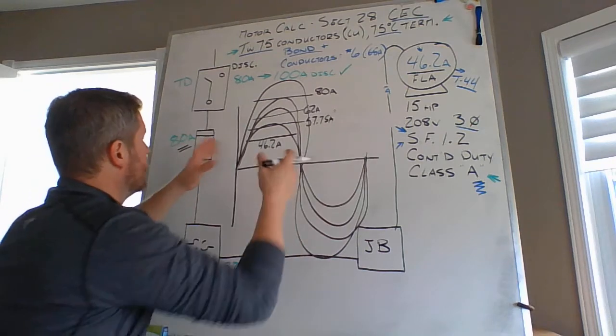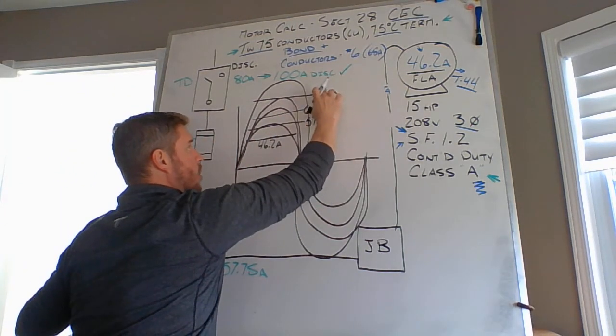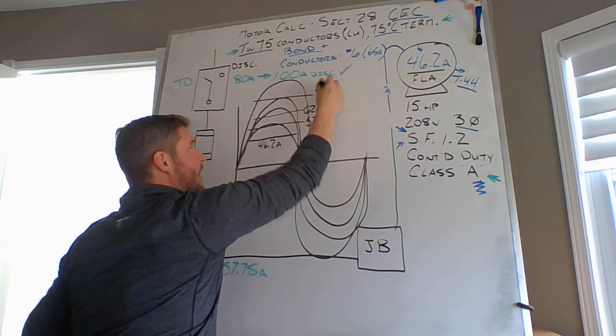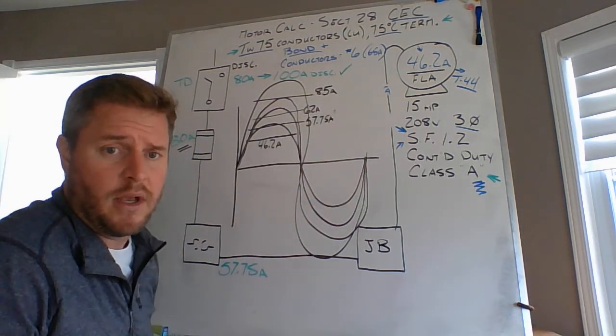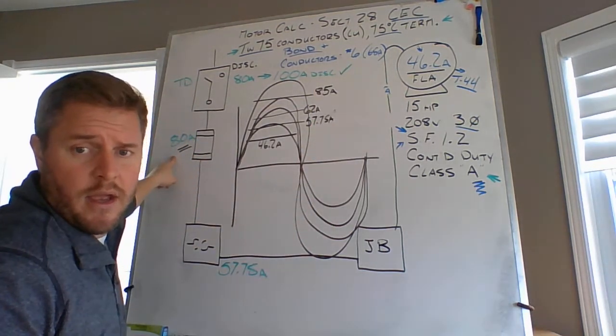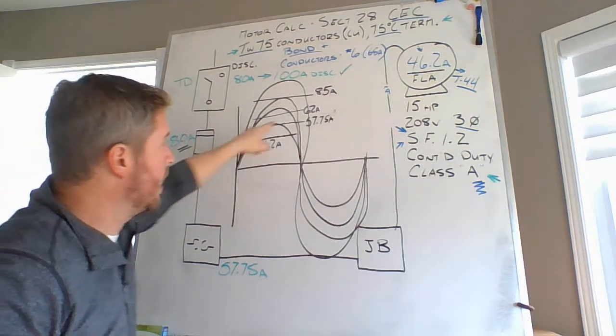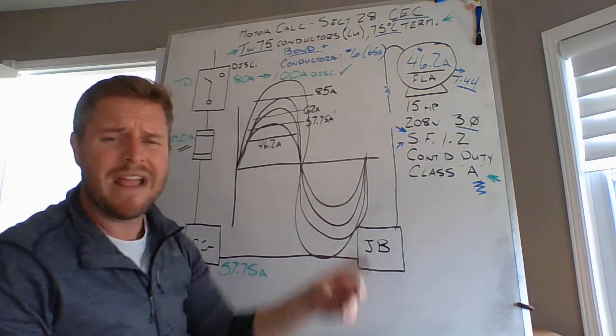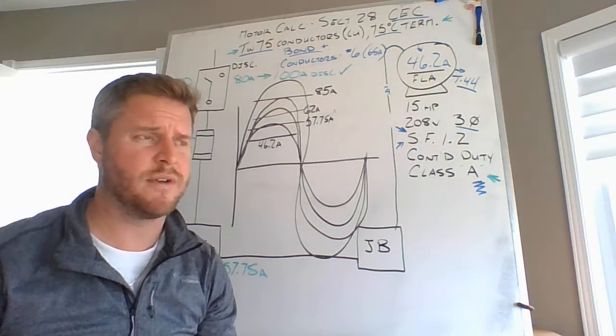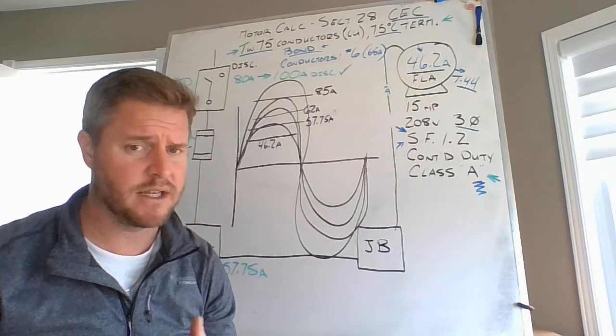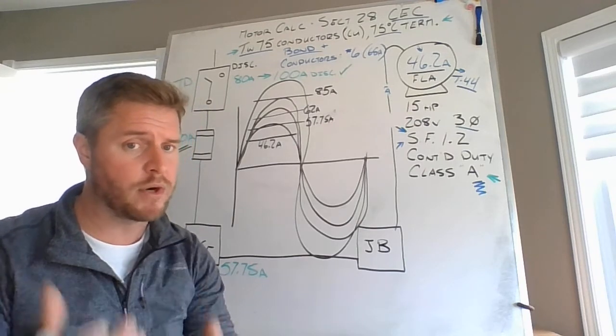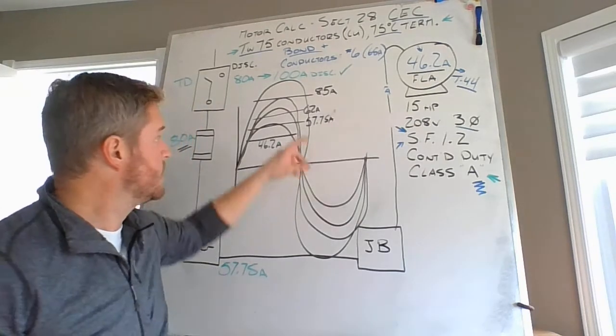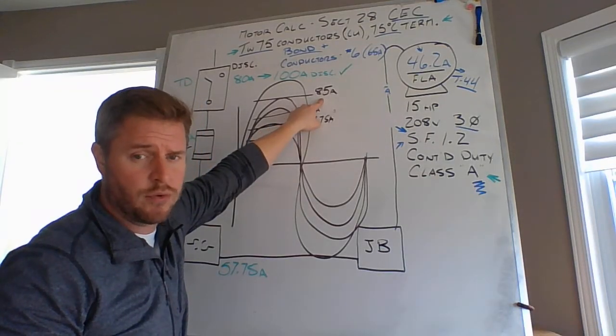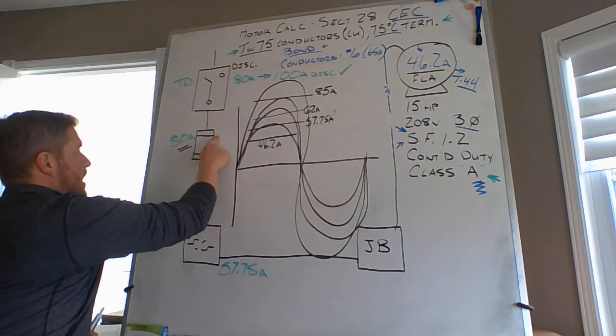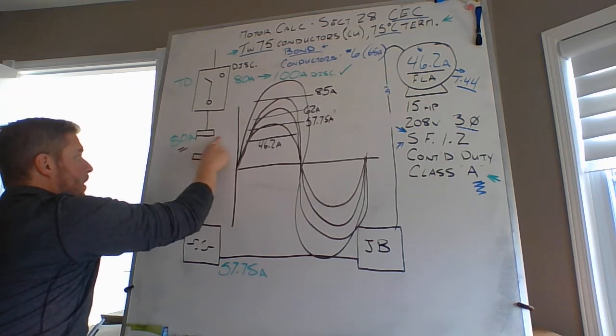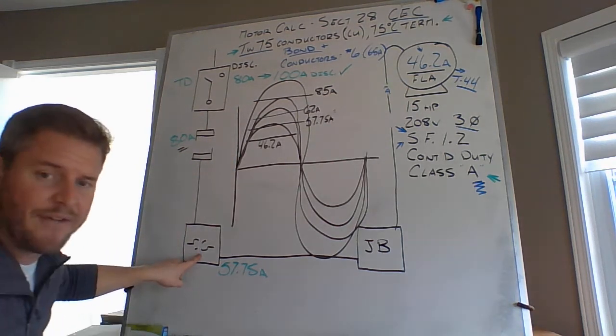So maybe all of a sudden this motor is drawing far too much current and you bump up to 85 amps as an example. Your time delay fuses are going to say, that's okay. I am a time delay fuse, so I'm going to allow that current for a very short period of time. That might be anywhere between 2 to 15 seconds, to allow that motor to get up to rated speed. But as soon as it sees that 85 amps for far too long, that overcurrent device itself will open if your overloads haven't already.